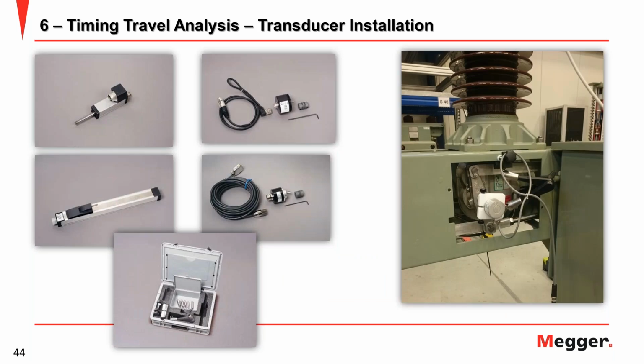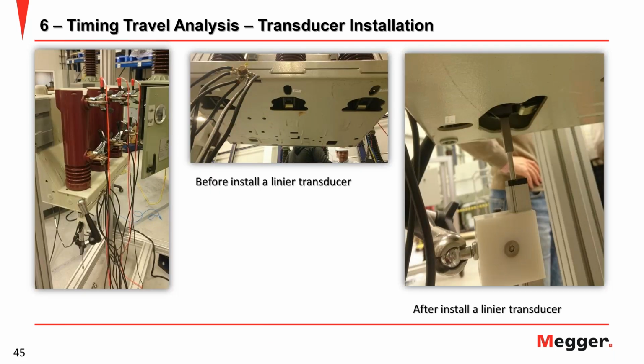This is the sample of the transducer, and generally all brand tester will provide you the same transducer. This is the rotary transducer, this is the linear transducer, depending on how much the length of the stroke inside the breaker, and this additional part to be used to connect our transducer. This is an example of how we install the transducer.